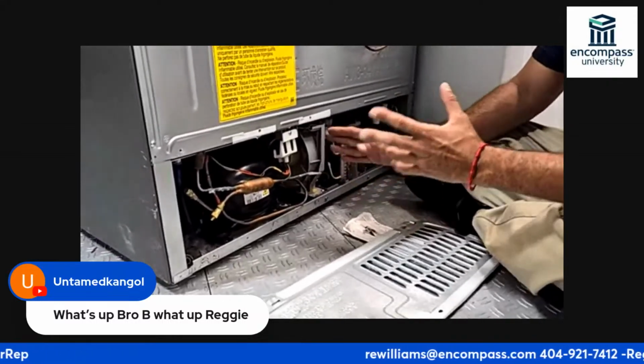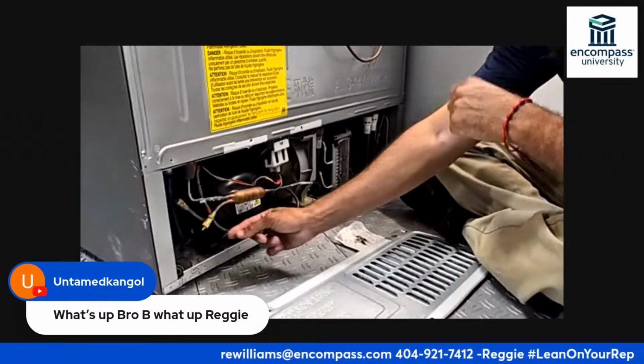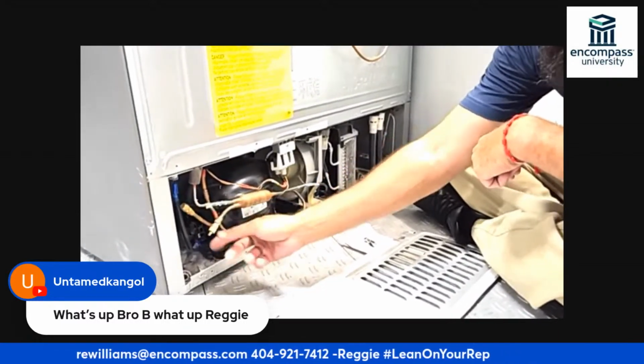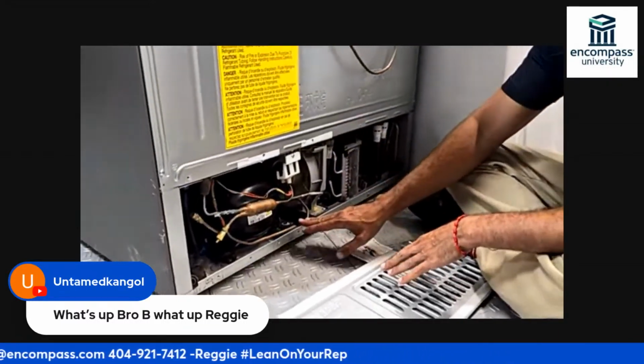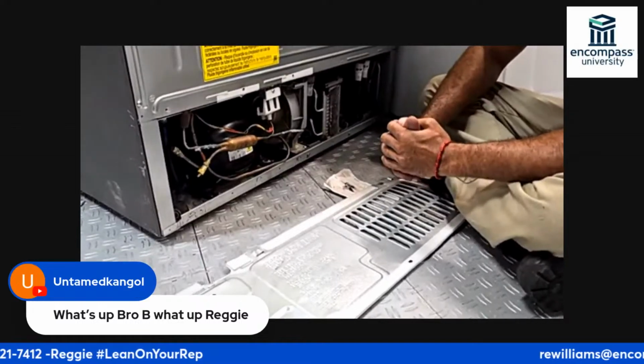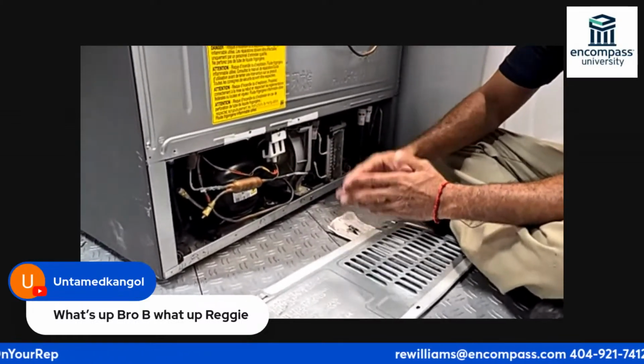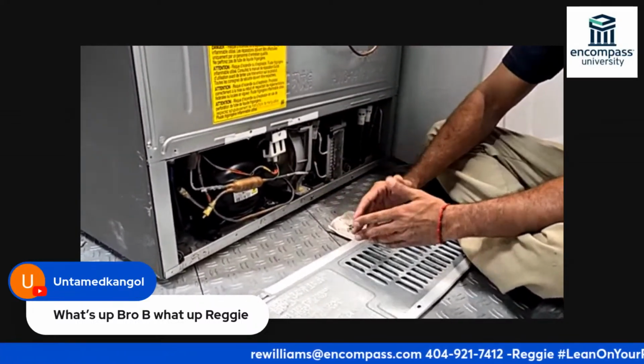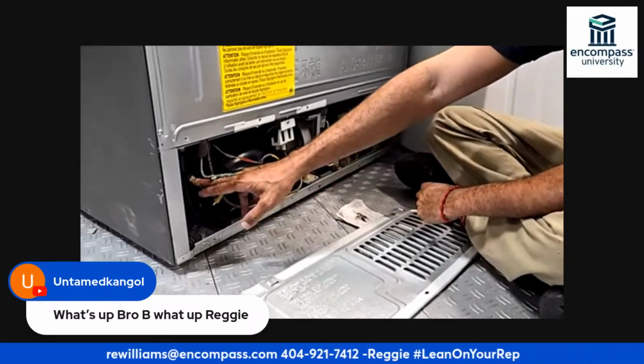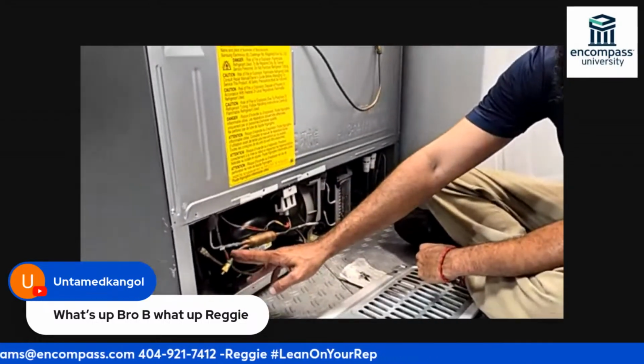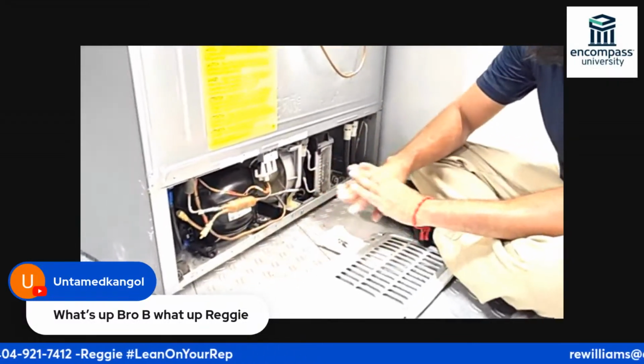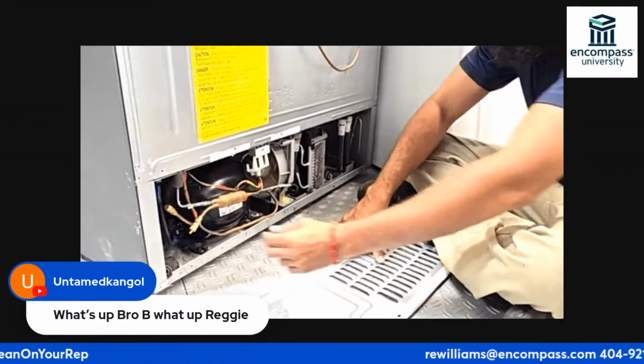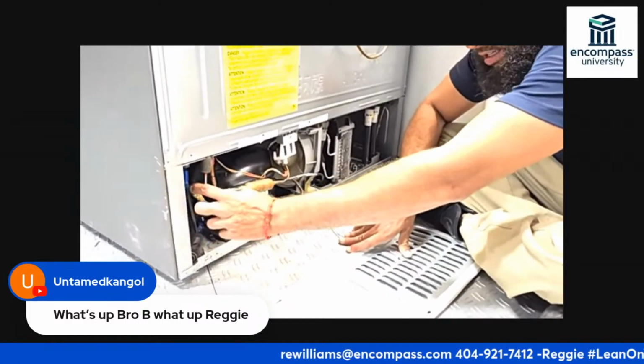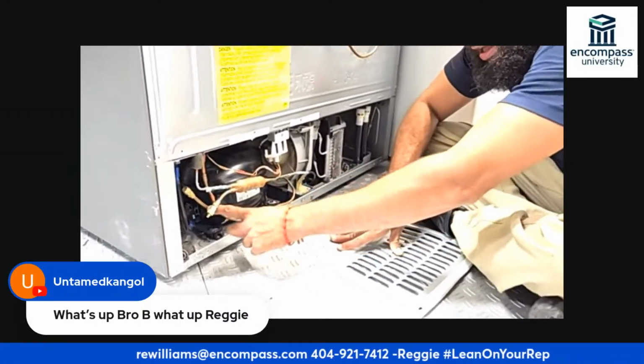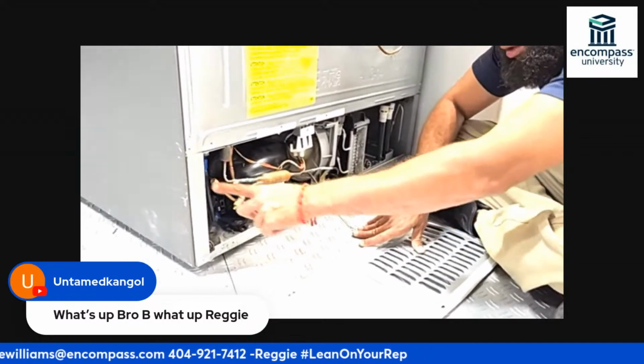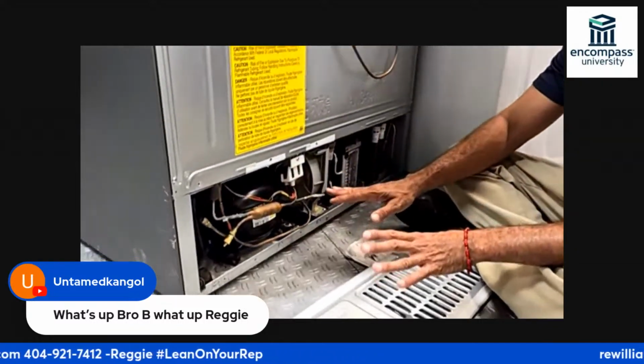Another thing I'm looking at here is these little fittings. This tells me somebody has been back here before, that this unit has had some sealed system work done to it, because typically manufacturers don't leave these on, they cut them up, pinch them off, and leave the system completely sealed. By seeing this, it means somebody changed this compressor and did their work through here. That's something to consider.